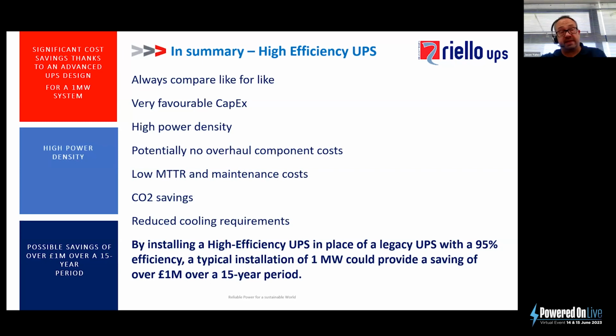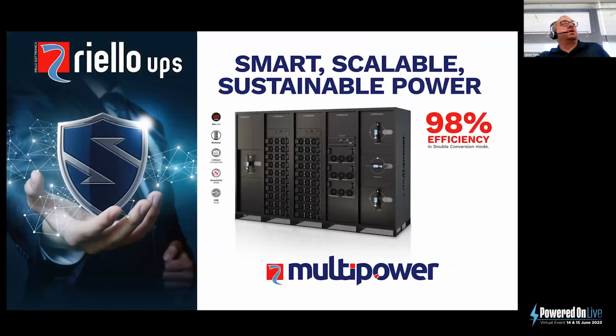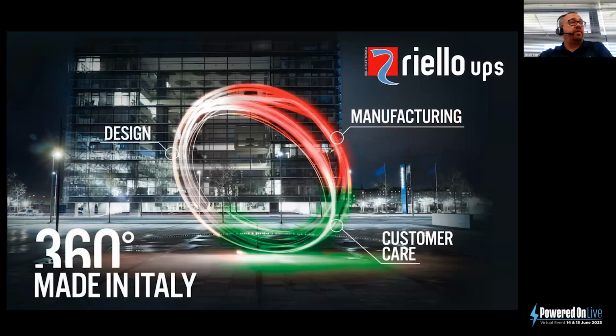Even at 95% efficiency, we're replacing UPS in the field of up to as low as 88% at the moment. A typical installation of 1 megawatt could provide a saving of over £1 million over a 15-year period. So it's obviously significantly worth it, and the payback is significantly quicker than it would be with a lower efficiency UPS system. So that is the Multi Power high efficiency UPS, designed and manufactured by Riello UPS in Italy.